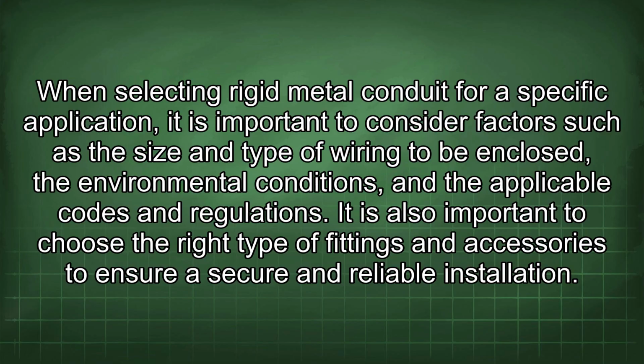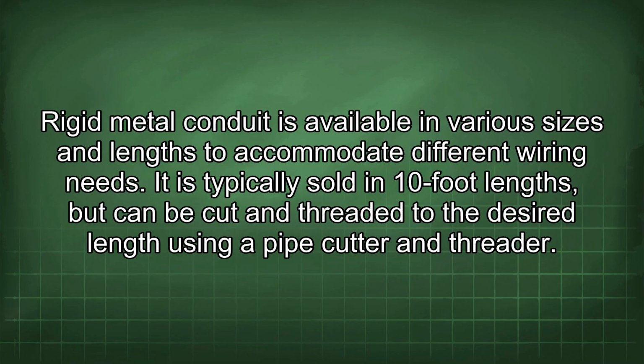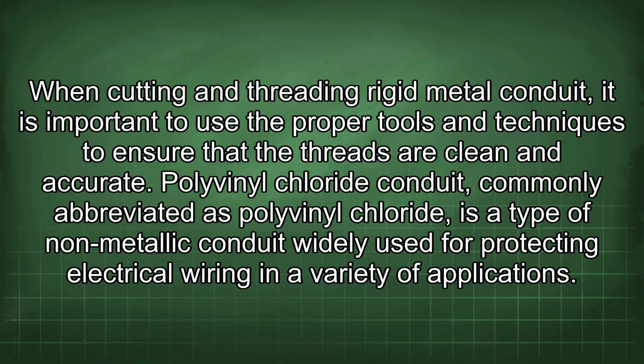It is also important to choose the right type of fittings and accessories to ensure a secure and reliable installation. Rigid metal conduit is available in various sizes and lengths to accommodate different wiring needs. It is typically sold in 10-foot lengths, but can be cut and threaded to the desired length using a pipe cutter and threader. When cutting and threading rigid metal conduit, it is important to use the proper tools and techniques to ensure that the threads are clean and accurate.